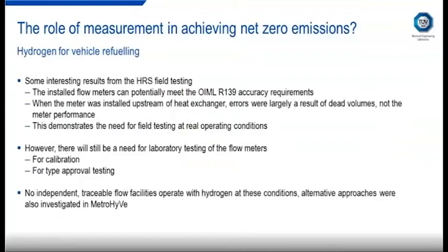But the general findings are fairly interesting. We can see that potentially the flow meters installed at the refueling station can meet the requirements of the OIML R139 standard. But there is a caveat to this, and that is the fact that there are many sources of measurement uncertainty, which can actually increase the error quite dramatically. So there are things that have to be taken into account, such as dead volumes and the effect of temperature, for example. But it demonstrates that there is a need to go to the refueling stations and test under real conditions using these types of systems. At the same time, there's still a need to test the flow meters in isolation, not so much the refueling station as a measurement system.